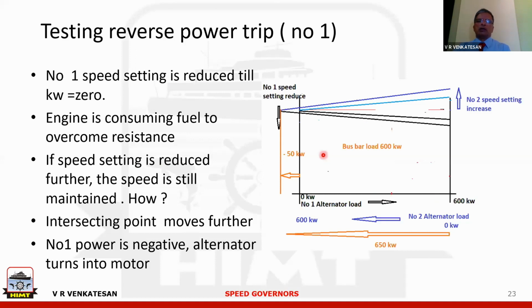Now the droop line also shows how reverse power trip is tested. How do we test reverse power? It is like this. You want to test reverse power on number 1 alternator. Number 1 alternator is shown by the black line. So this point shows number 1 speed setting is reduced till the kilowatt has become 0. So here it has become 0. It is not producing any electrical power, but the engine is still consuming fuel. Why is it consuming fuel? To overcome frictional resistance. Because there is resistance. The resistance is still there.